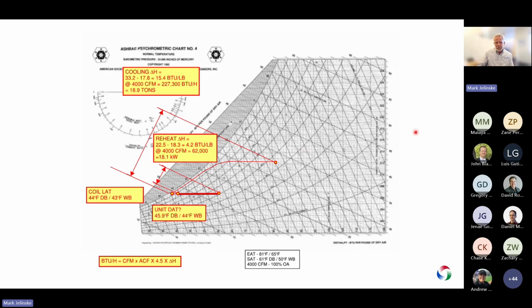What we'd probably end up recommending, what I'd talk to you about, we're not going to reheat this stuff, are we? No, we can propose to use a unit that comes with hot gas reheat. That's a very common packaged unit that, as part of the refrigeration cycle, takes the heat that we are already going to reject through the condenser to the exterior and to the ambient air, and has a separate coil in the supply airstream that takes some of that heat and reheats that air.